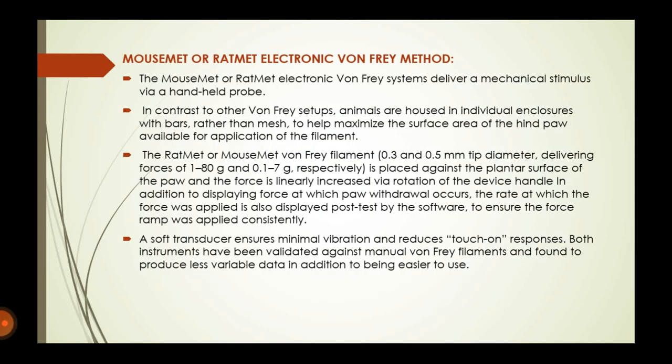The MouseMet or RatMet is the only Von Frey system with a force range intended specifically for mice. Its rotary force transducer has a range of 0.1 grams to 7 grams of force. This system has been extensively validated and makes a considerable contribution to the three R's. A soft transducer ensures minimal vibration and reduces touch-on responses. Both instruments have been validated against manual Von Frey filaments and produce less variable data while being easier to use.